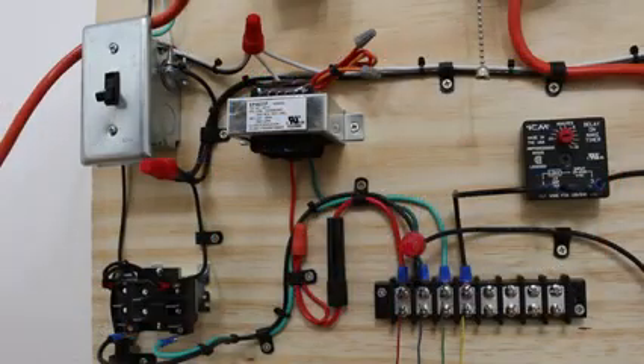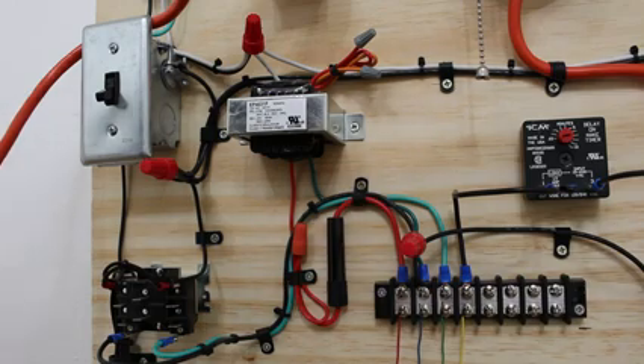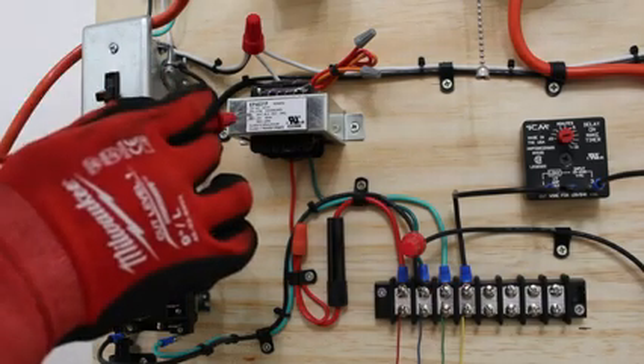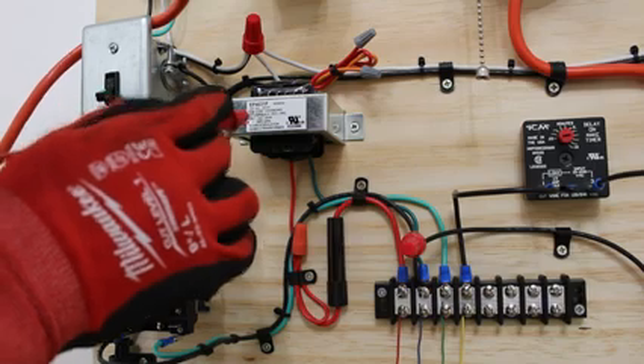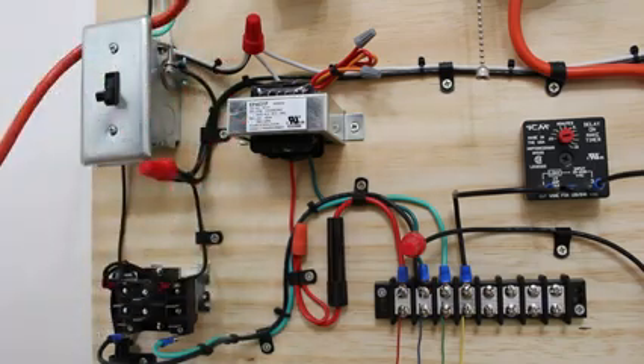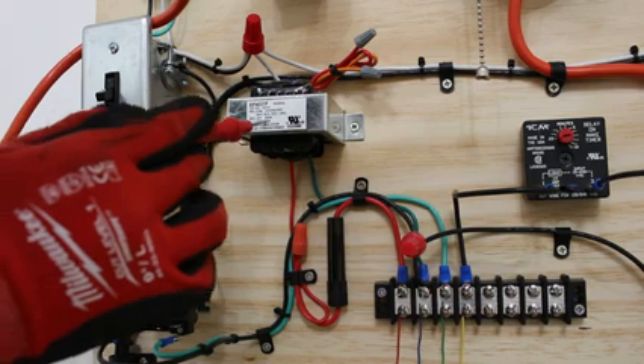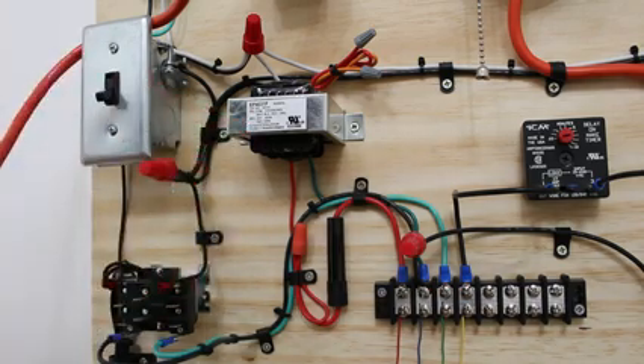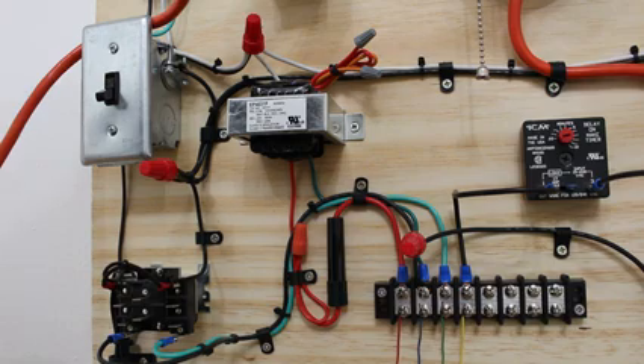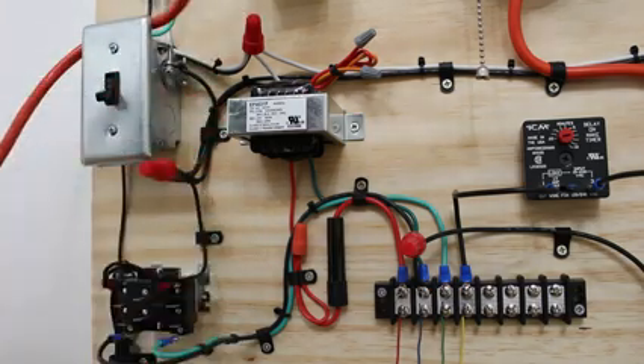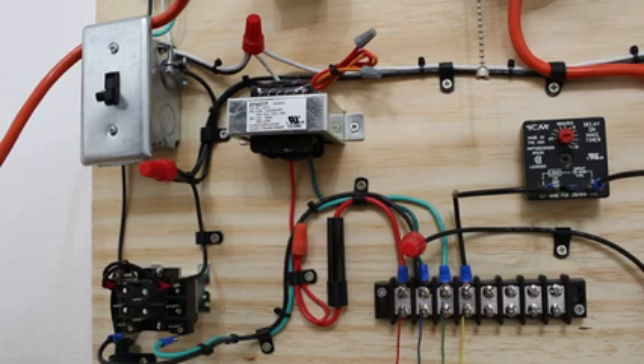To keep things simple, the way to check a transformer is to first identify, if you can, what is your primary voltage, see which colors they are, and make sure you have your primary voltage. Check your secondary voltage and make sure you have your secondary voltage. If you do, then of course your transformer is good. I'm going to end off this video with a couple tips. If you have your incoming voltage and you have no secondary voltage right away, your transformer is bad.